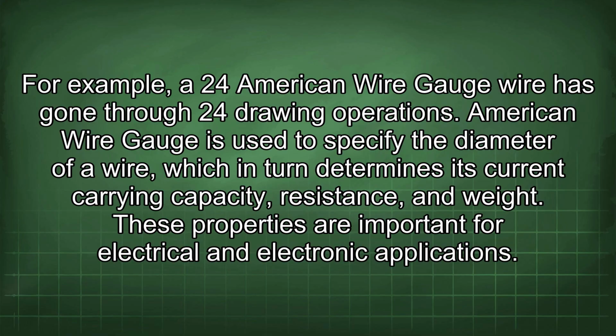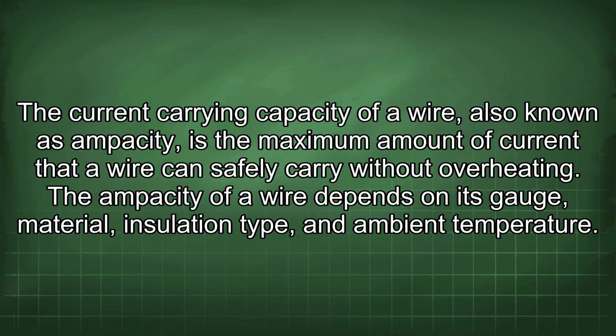American wire gauge is used to specify the diameter of a wire, which in turn determines its current carrying capacity, resistance, and weight. These properties are important for electrical and electronic applications. The current carrying capacity of a wire, also known as ampacity, is the maximum amount of current that a wire can safely carry without overheating. The ampacity of a wire depends on its gauge, material, insulation type, and ambient temperature.